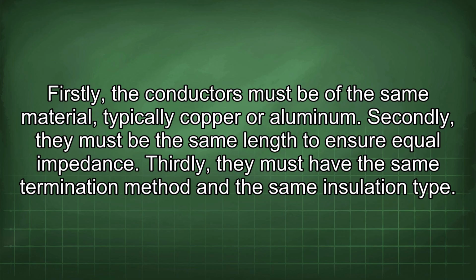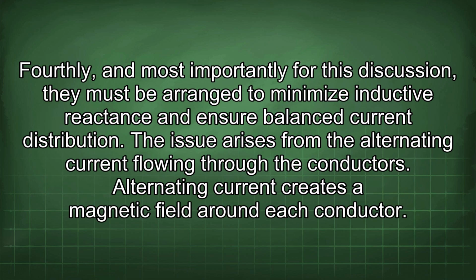Firstly, the conductors must be of the same material, typically copper or aluminum. Secondly, they must be the same length to ensure equal impedance. Thirdly, they must have the same termination method and the same insulation type. Fourthly, and most importantly for this discussion, they must be arranged to minimize inductive reactance and ensure balanced current distribution.